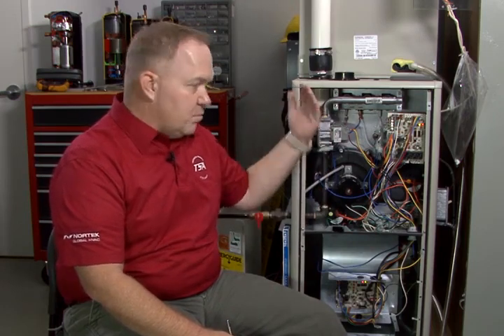If it does not see that the motor is communicating properly, it's going to interrupt and suspend the ignition sequence so that the furnace will not fire and then just sit there and try to cycle itself in and out as far as a limit control is concerned. So be aware that if you have a two-stage gas furnace with an ECM motor in it, or a single stage that has been upgraded to variable speed, when it starts the ignition process, it is going to begin looking for the motor early within that ignition sequence.